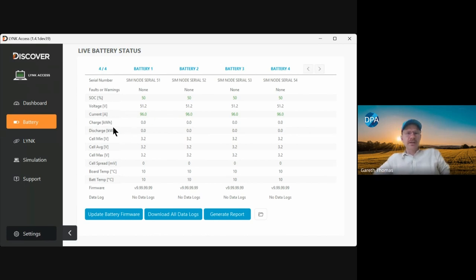It's really valuable data. You can also see the charge and discharge kilowatt hours, so you can see how much work each battery in the stack has done over its lifetime. Again, if you were troubleshooting a battery bank and saw one of these values much greater than the others, that would indicate that one's working harder and there's some sort of issue.